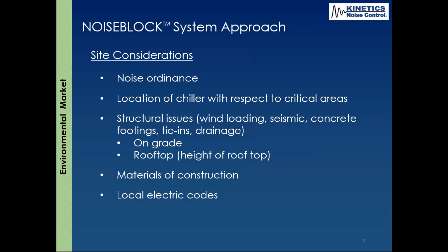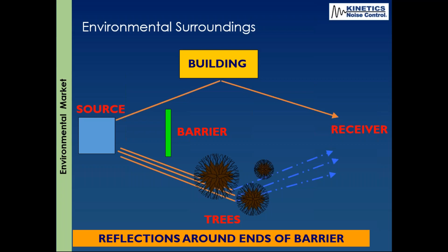Looking at environmental surroundings, there will be reflections all over, so the acoustical consultant wants to know the site conditions. For example, if the source is an air-cooled chiller and there's a barrier wall of a certain length, in plan view you have to be careful of noise flanking around the wall. The receiver may not have direct line of sight to the source, but nearby reflective items can flank noise around and short-circuit your noise control—something the acoustical consultant watches for.